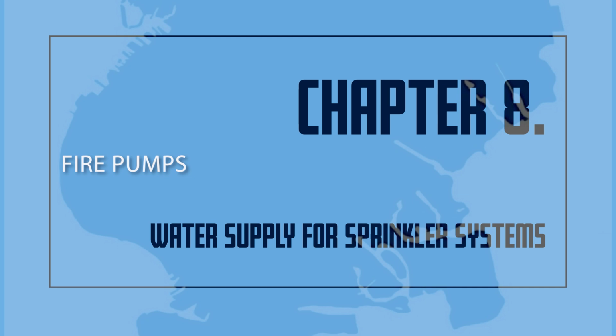A fire pump having both a reliable source of power and a reliable suction water supply is an effective piece of equipment. A suction water supply is simply a body of water that the pump can draw water from. Fire pumps are commonly used because they can pump water into the sprinkler system under high pressure. With a good water supply, a fire pump can pump water into a sprinkler system for a long time. Manually started pumps may be used as a secondary supply source if the primary water supply will last long enough to allow the pump to be started.